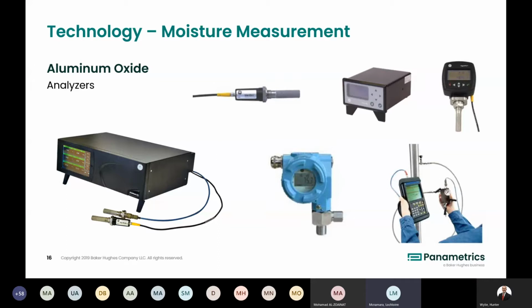Underneath that, in the bottom right-hand corner, you've got what's called the PM880. That's our portable moisture analyzer. You'd hook that electronics up to one of the sensors you've seen on the previous slide, and it allows you to make moisture measurements on the go. It's intrinsically safe, battery powered, with 8 to 12 hour battery life, data logging, multifunction, portable, a very rugged, very dependable analyzer.